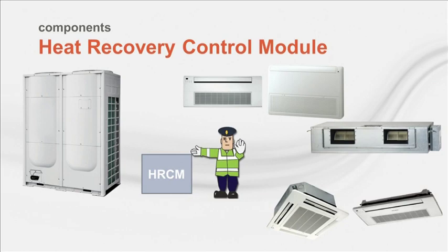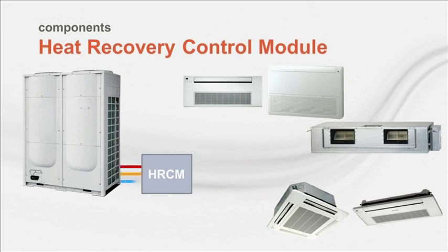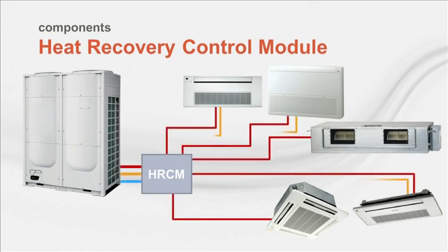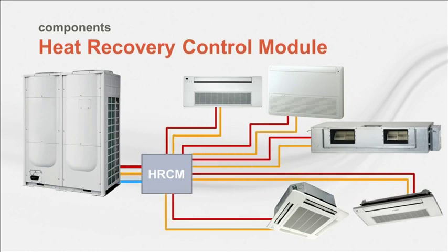Of course, this requires sophisticated controls that are able to relay the desire for heating or cooling to the refrigerant traffic police. The module is connected to the outdoor unit, and a series of refrigerant lines is run to each indoor unit. In this example, each indoor unit is providing warm supply air to each space.